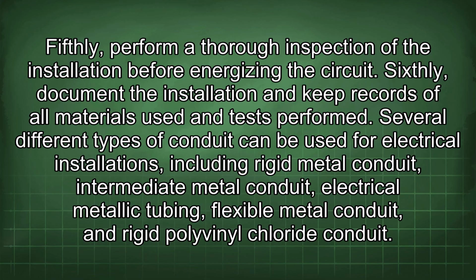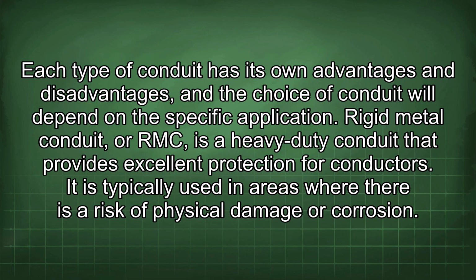Several different types of conduit can be used for electrical installations, including rigid metal conduit, intermediate metal conduit, electrical metallic tubing, flexible metal conduit, and rigid polyvinyl chloride conduit. Each type of conduit has its own advantages and disadvantages, and the choice of conduit will depend on the specific application. Rigid metal conduit, or RMC, is a heavy-duty conduit that provides excellent protection for conductors. It is typically used in areas where there is a risk of physical damage or corrosion.